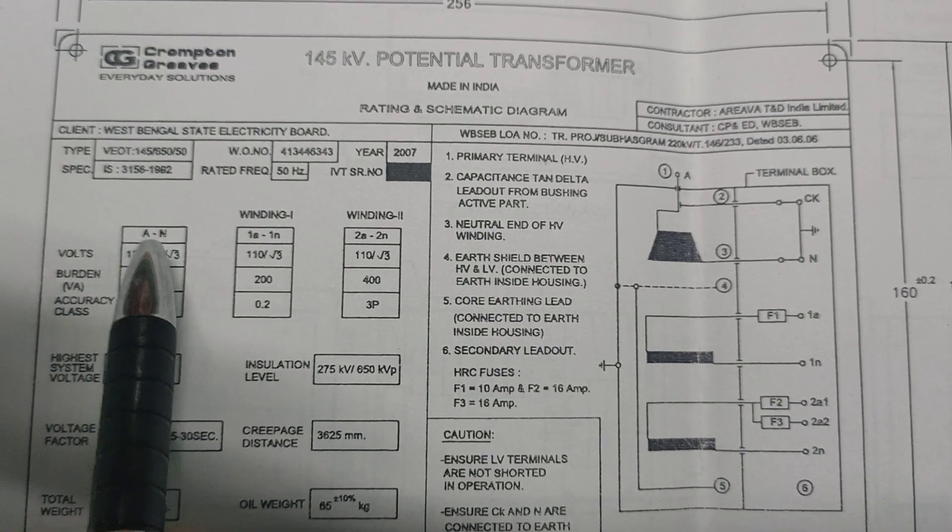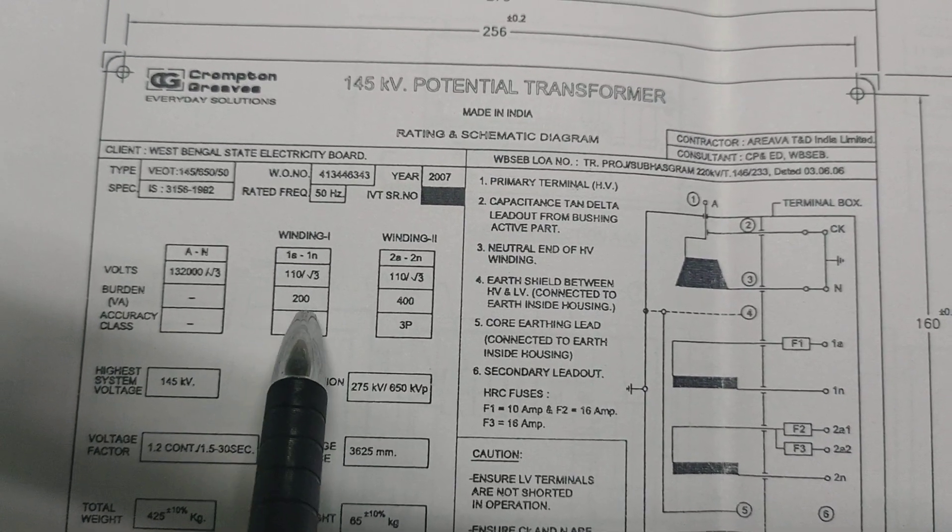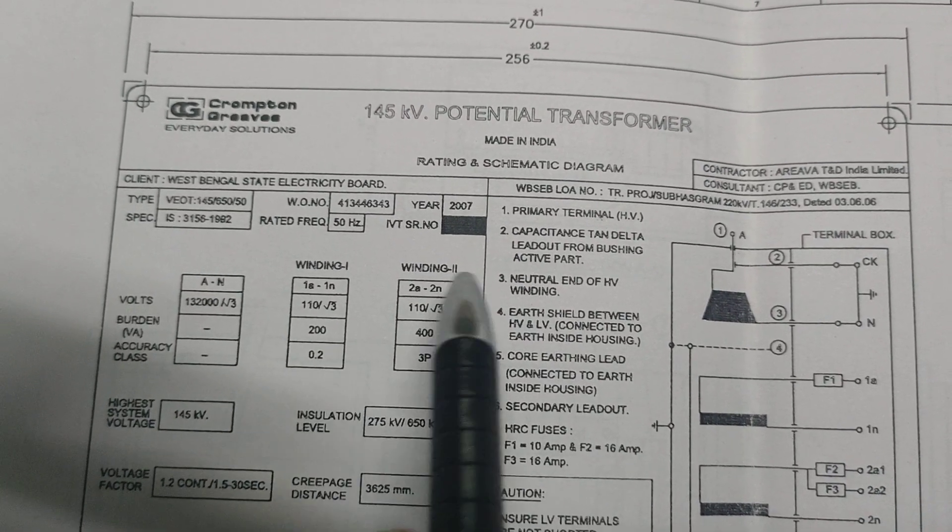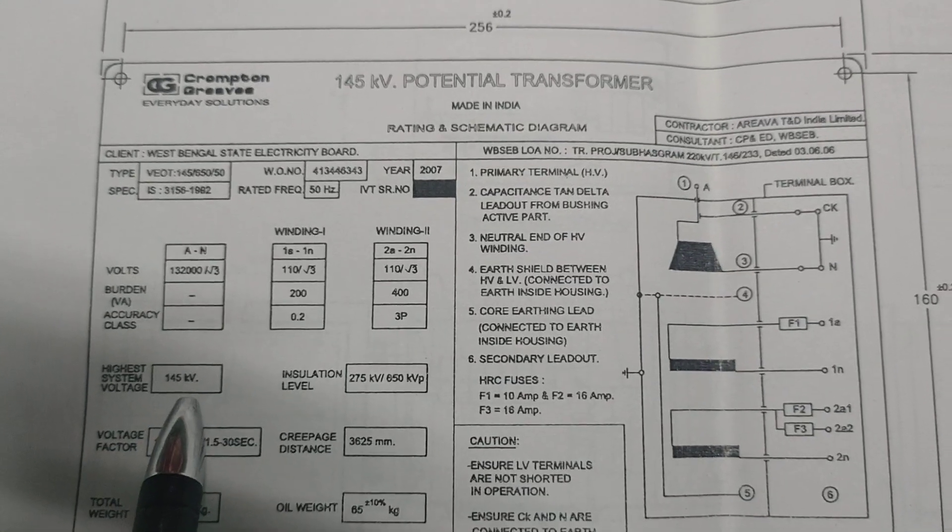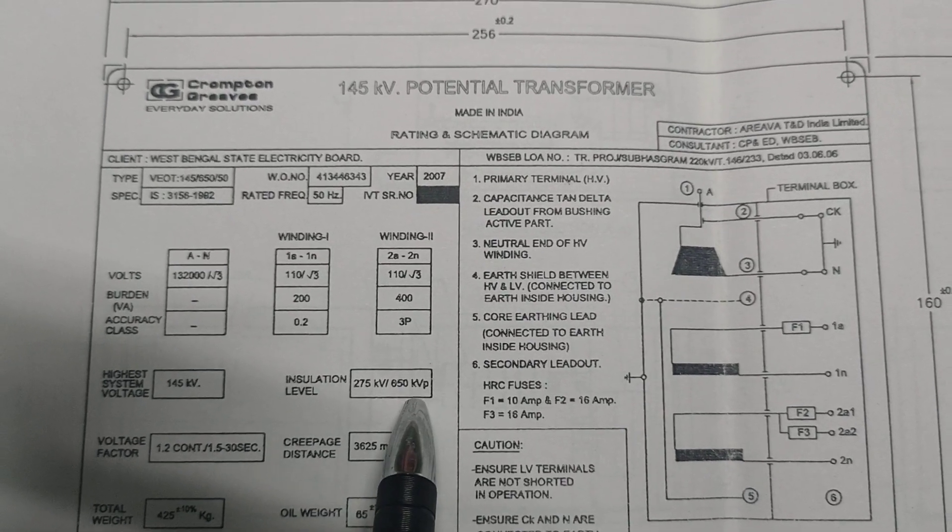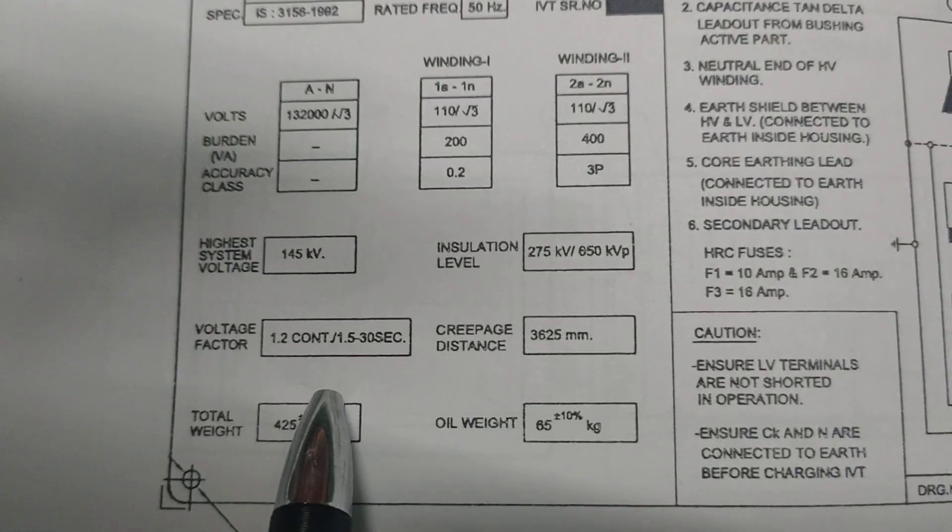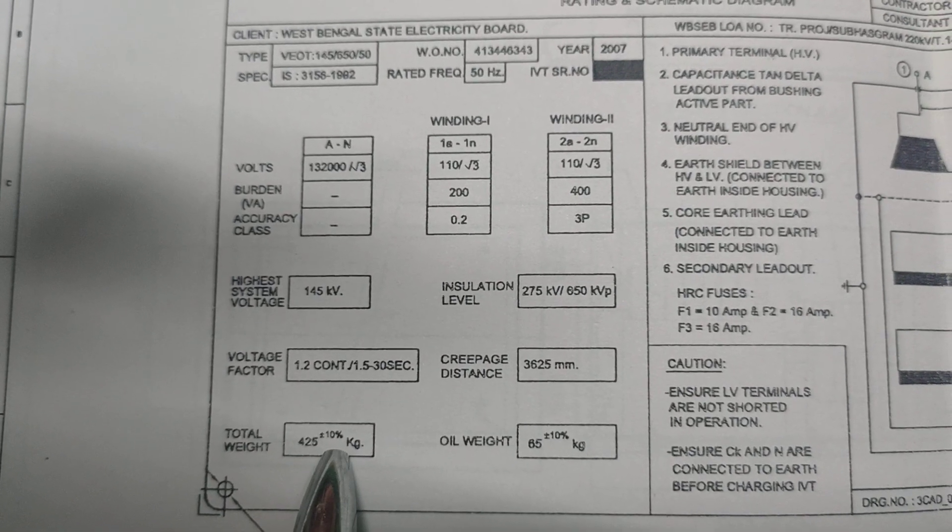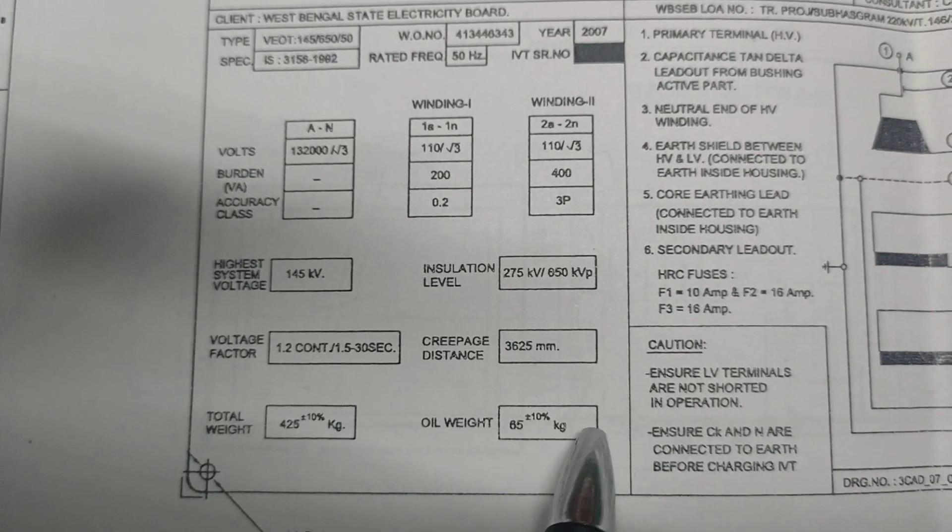The burden of winding 1 and winding 2: the primary winding has no burden and no accuracy, and the winding 1 and winding 2 has an accuracy level and also the burden. Winding 1 has a burden of 200 VA and winding 2 has a burden of 400 VA. Winding 1 has 0.2 accuracy class and this is 3P accuracy class. The highest system voltage is 145 kV. Insulation level is 275 kV oblique 650 kVp. Voltage factors 1.2 continuous to 1.5 for 30 seconds. Total weight is 425 plus minus 10 percent kg. Oil weight is 65 plus minus 10 kg. Creepage distance 3625 mm.